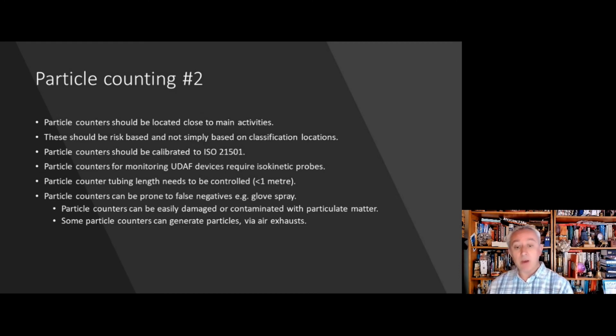We also need to verify that our particle counter itself is not pumping out contamination, so studies of the air exhaust around particle counters are of great importance and I recommend them to be conducted.